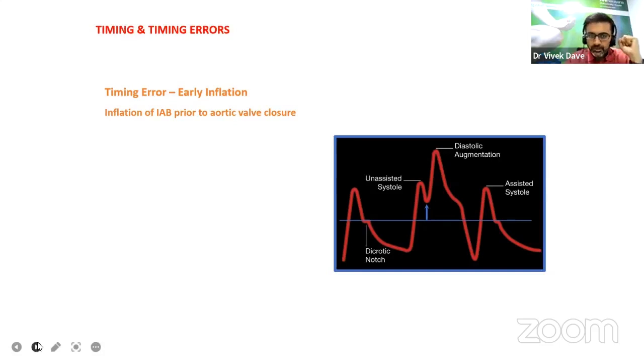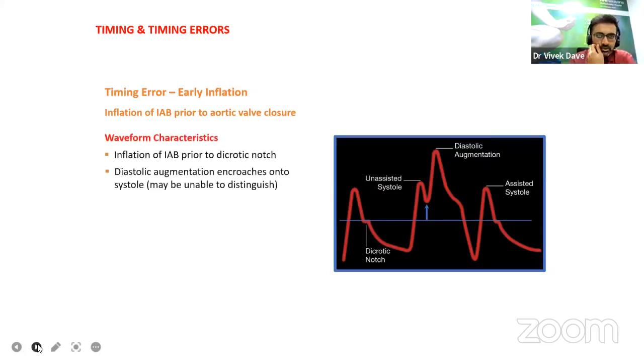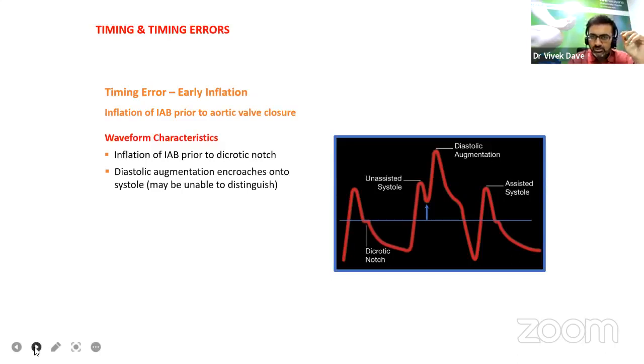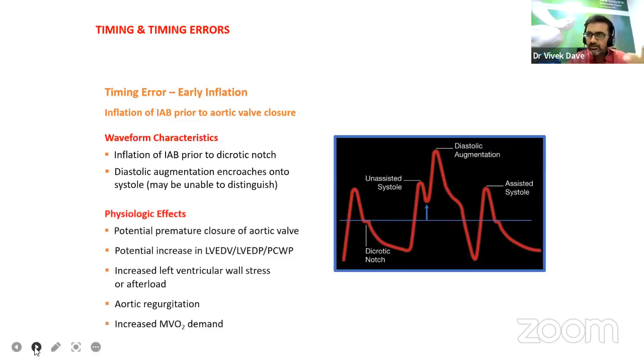Timing error: when there is early inflation — inflation of IABP prior to aortic valve closure — the waveform characteristics show inflation prior to dicrotic notch and diastolic augmentation encroaches onto systole. Physiologic effects of early inflation include potential premature closure of aortic valve, potential increase in left ventricular end-diastolic volume, increased left ventricular wall stress, aortic regurgitation, and increased oxygen demand.